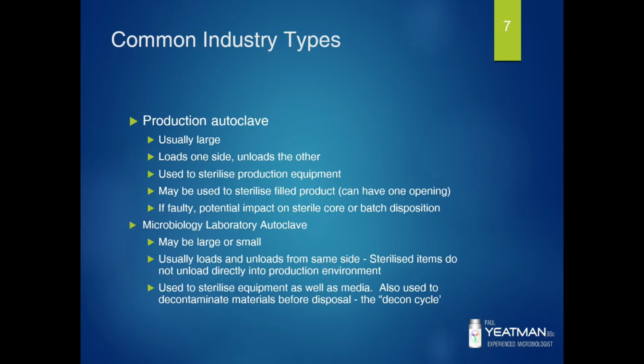So the production autoclave is usually big because you've got to autoclave a lot of stuff that goes into the production area. You'd load it up one side, say in your mixing room or your container prep room, and unload in the other side, which would be like your class 100 or class 10,000 zone, depending on your setup. It's used to sterilise production equipment. It might be used to sterilise filled product after a batch, so in that case you could have one opening if you wanted. You load it up within the filling room and unload it in the filling room. Alternately, you can load up in the filling room and unload it on the other side, like in your mixing room or filled product zone.